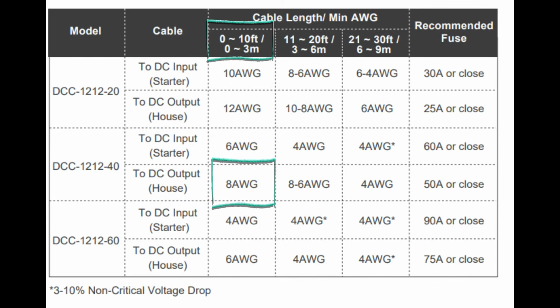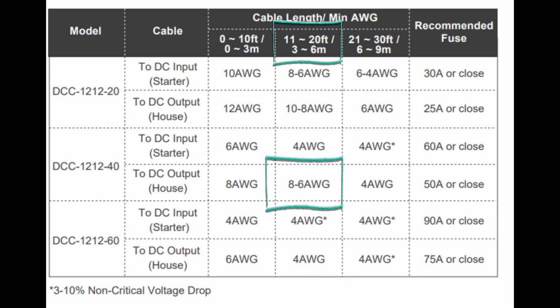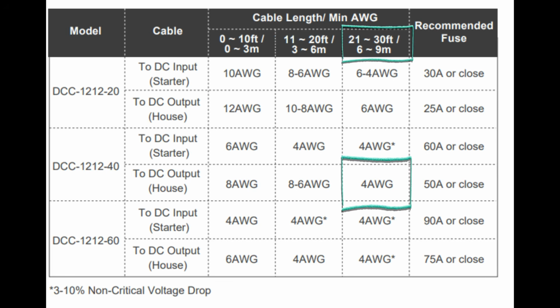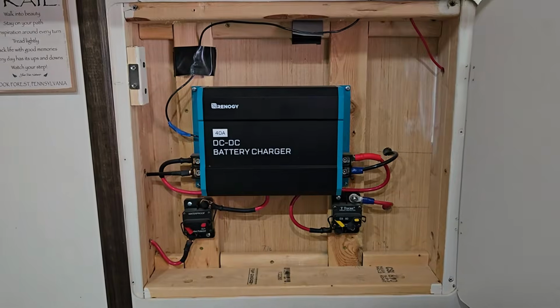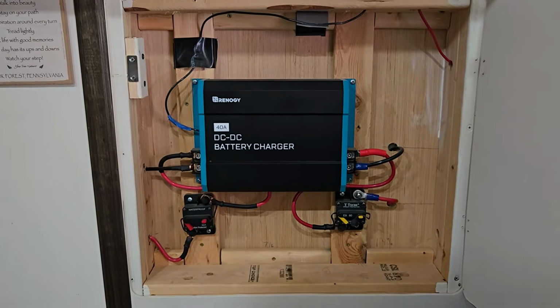If your house batteries are 10 feet or less from your DC to DC charger, use 8 gauge wire. If the charger is 11 to 20 feet, use 6 or 8 gauge wire. Finally, if your charger is more than 20 feet from your house batteries, use 4 gauge wire. Our charger was less than 10 feet from our house batteries, but we ended up using 6 gauge wire instead of 8 gauge because we had it on hand.